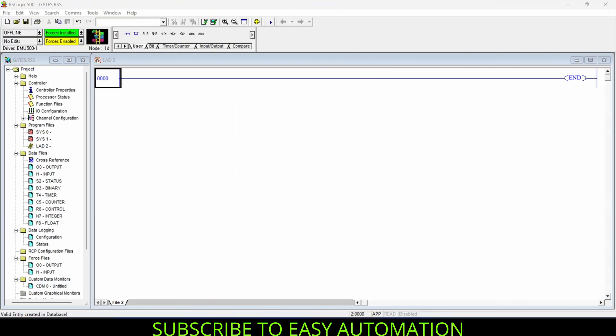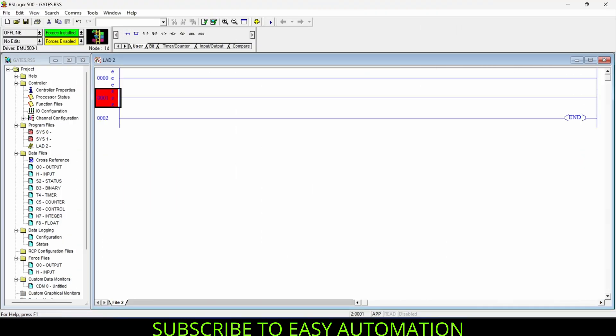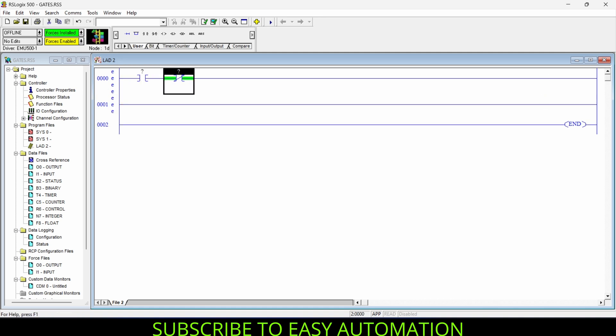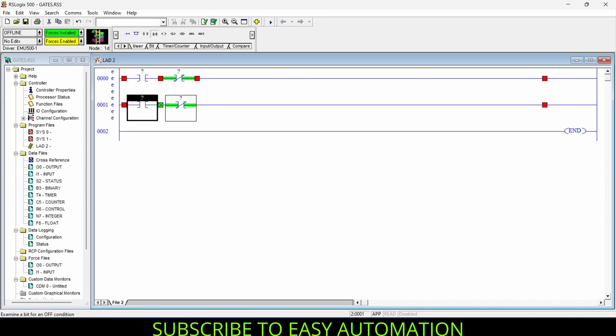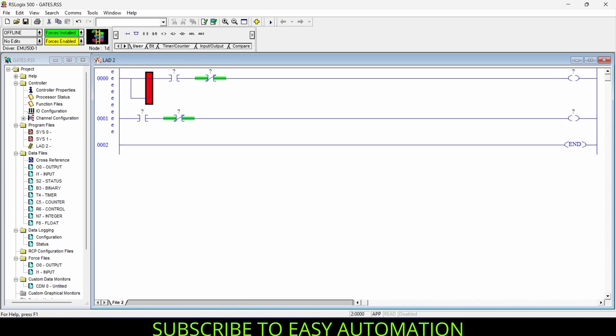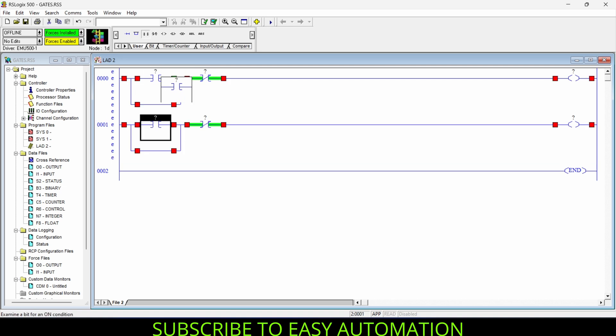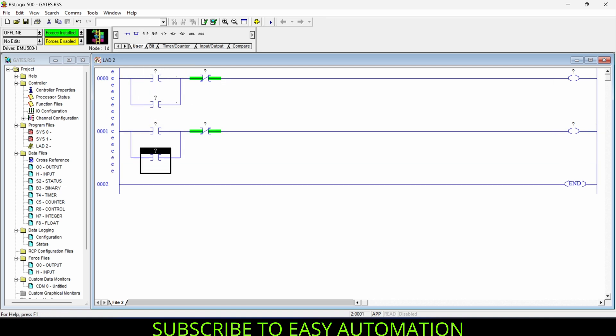The program is very basic. We need two rungs — one for the upper motor and one for the lower motor. In the first rung I'll add one NO contact and one NC contact, and in the second rung as well one NO contact and one NC contact. In both rungs I'll add two output coils, add a branch instruction, put an NO contact inside the branch, and add two more NO contacts — this is how our program will look.